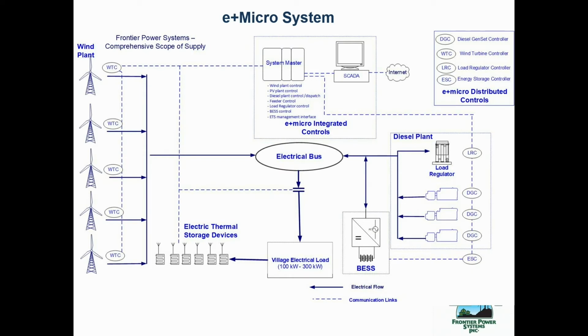We call that the minimum operating load. If we go lower, we run into risks of damaging the engine. So if the load on the village doesn't change, but the wind turbines supply more power, we send that power to the load regulator to be consumed as a fail-safe.